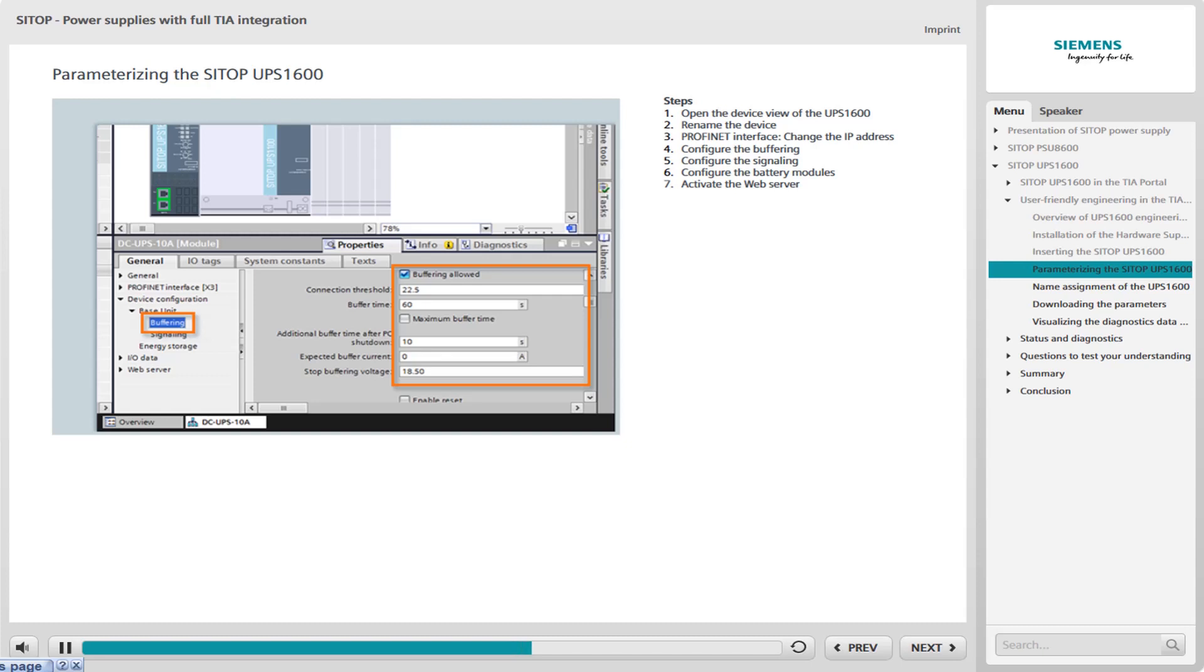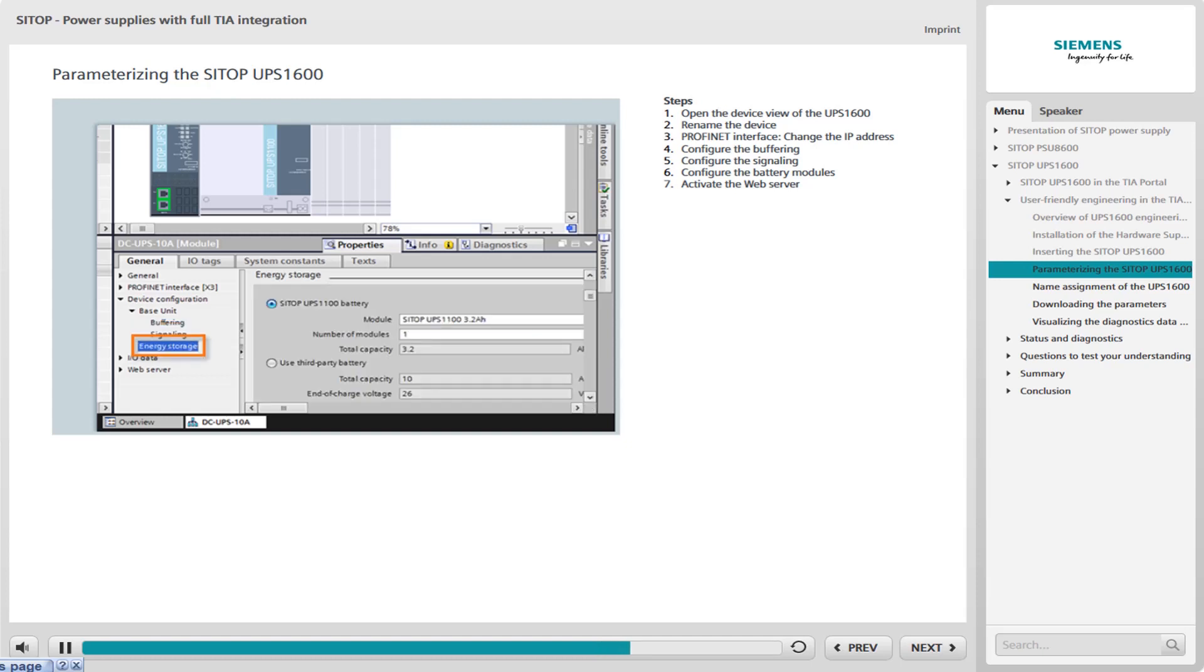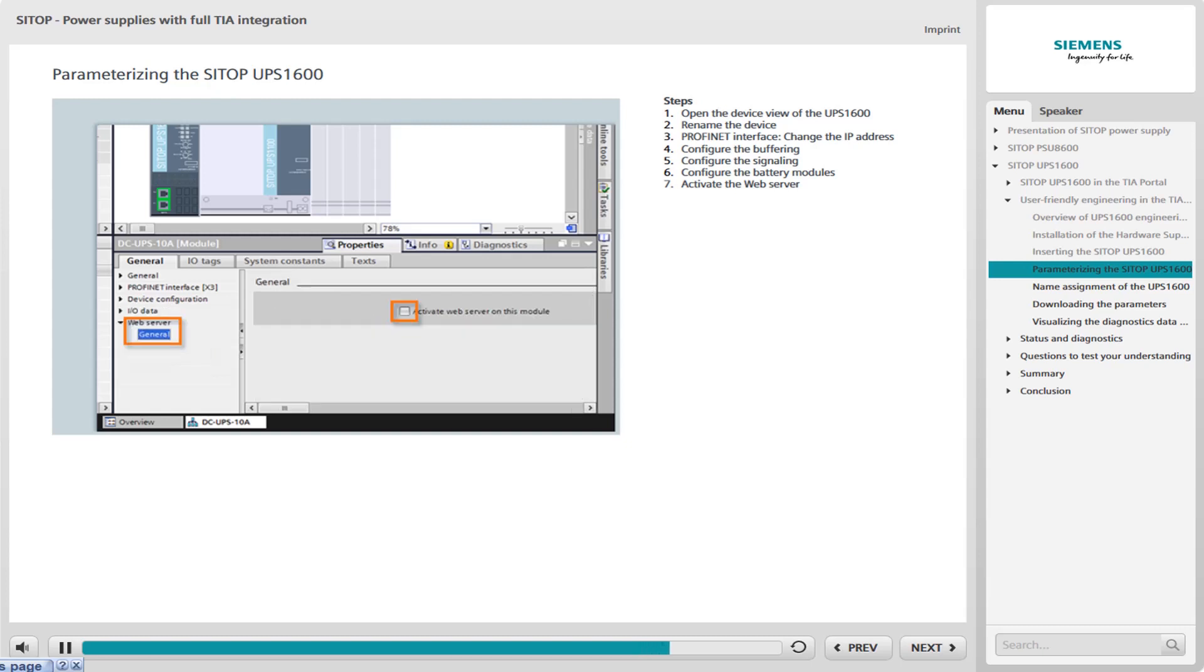You set the parameters for the UPS in the Device Configuration area. In the example, the buffer time is set to 60 seconds. You can set the wait time after which the alarm is to be transmitted following power failure. In this example, 125 milliseconds. In the Energy Storage area, add the battery modules and set the relevant parameters. In addition, you can activate the UPS 1600 web server. The web server is deactivated as the default. Set a check mark to activate it.